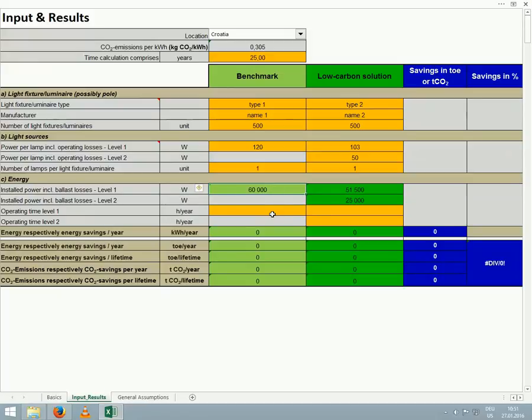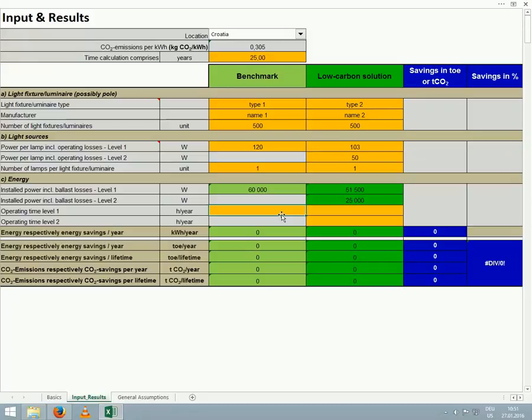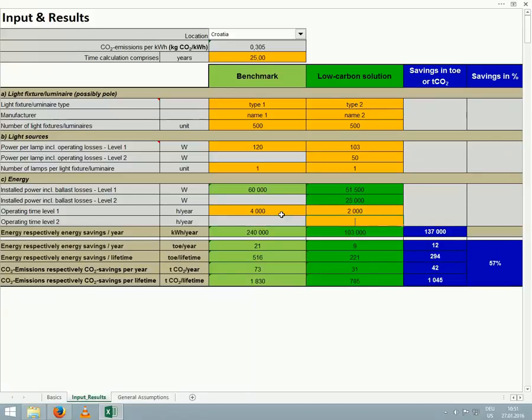Finally, we now enter the operating time in hours per year for our two street lighting options. Where we have two power levels present due to dimmable light fixtures, we split the total hours per year between the two. For our example, we enter 4,000 hours per year in level 1 for the benchmark, and for our low carbon solution, we enter 2,000 hours per year each in levels 1 and 2.